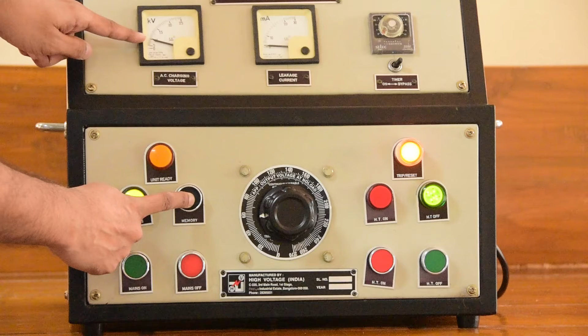Kindly focus your attention on the reading registered at the moment of failure for the test we just performed. By pressing the memory switch on the panel again, you should observe that the dial shows the last reading where the sample failed. Here you can see it is showing a voltage of 8 kV.